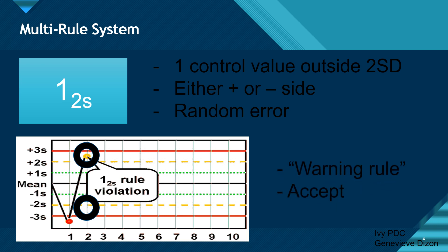The 1-2-S rule is known as the warning rule. You accept the specimen because it's just warning you that there might be something wrong. This would alert the technologist of possible problems. What you do next is start looking for errors — look at other controls or look at previous results. Do not reject the result; you can accept the result and continue with your testing.